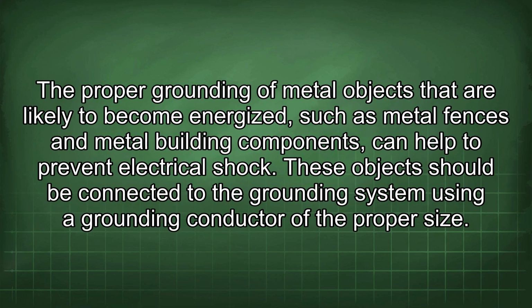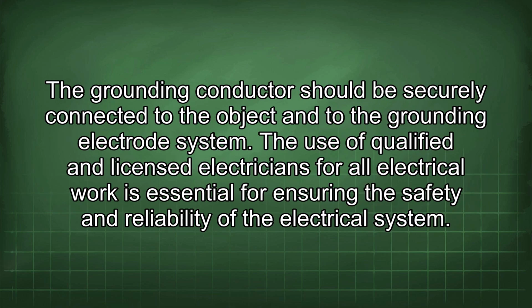The proper grounding of metal objects that are likely to become energized, such as metal fences and metal building components, can help to prevent electrical shock. These objects should be connected to the grounding system using a grounding conductor of the proper size. The grounding conductor should be securely connected to the object and to the grounding electrode system.